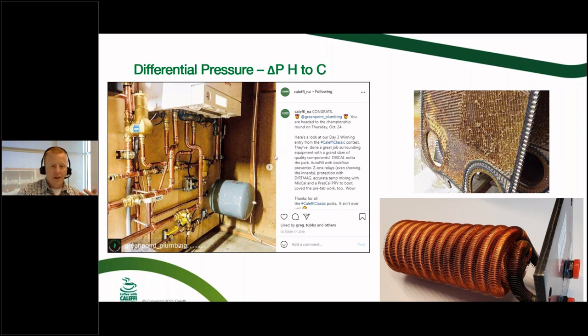So I know most of the combi manufacturers and the tankless water heater manufacturers are very vocal about maintenance and flushing out these guys and cleaning them out appropriately, on an annual basis or even twice a year. So make sure to do that, because again, the more pressure drop you get across that domestic hot water source, the less effective your mixing valve is going to be, is what it's going to boil down to. And this is something that we get quite a bit of calls about. So make sure that you have provisions, whether it be a tankless coil or a plate heat exchanger, to flush those guys out. Most of your tankless units and combis are going to have flush valves, or you're going to get them as an option, so you can flush those guys out with the appropriate cleaners.